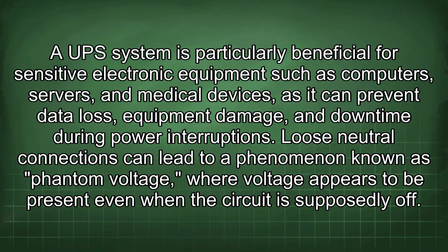Loose neutral connections can lead to a phenomenon known as phantom voltage, where voltage appears to be present even when the circuit is supposedly off.